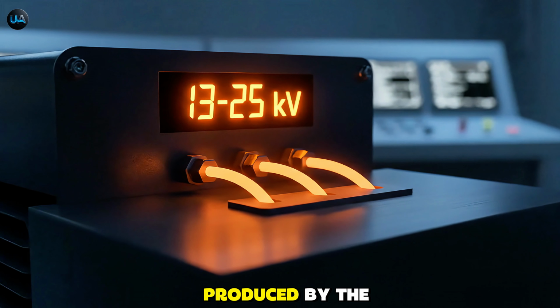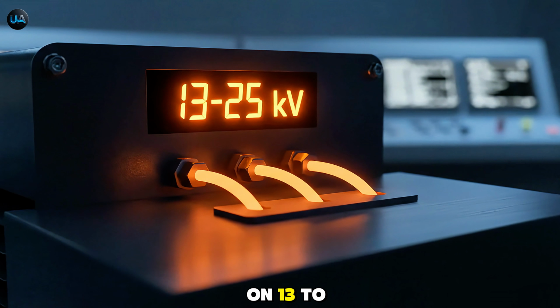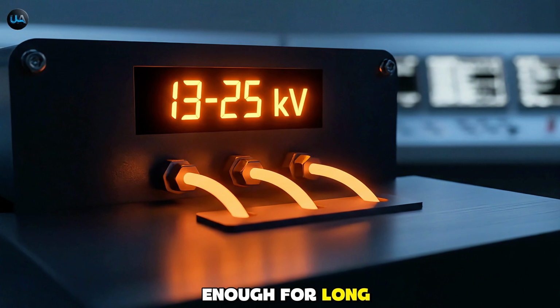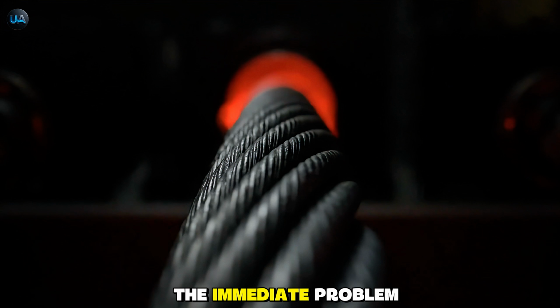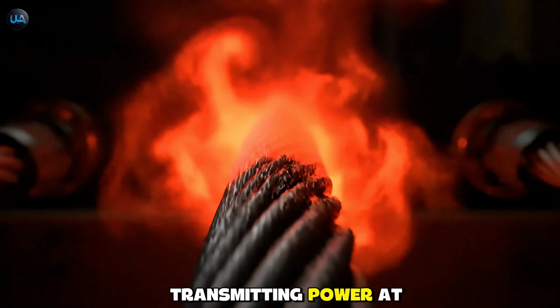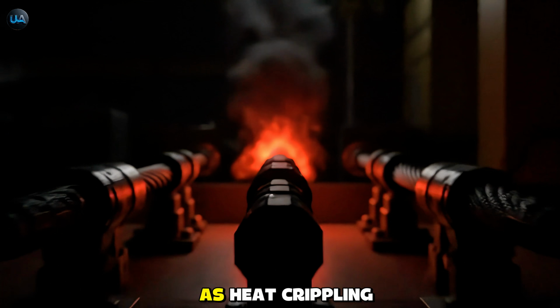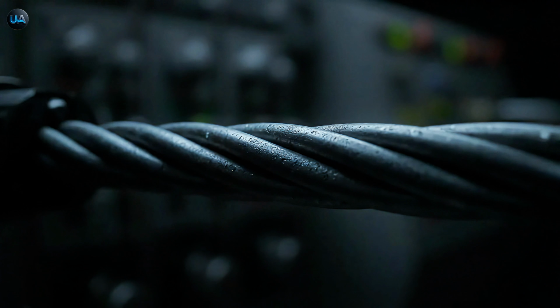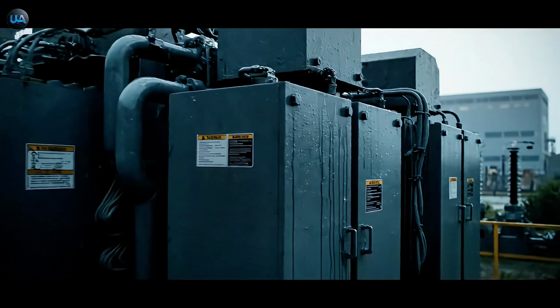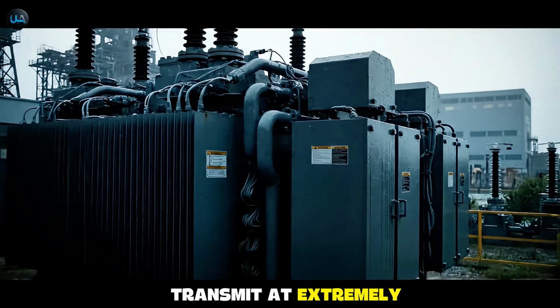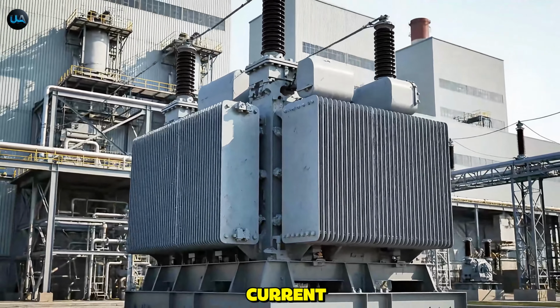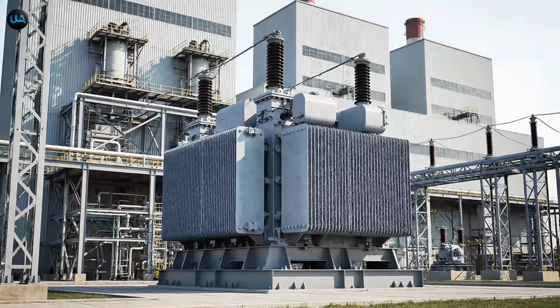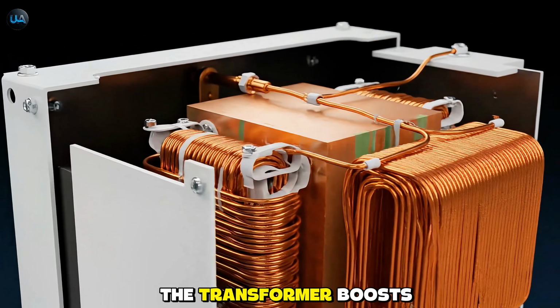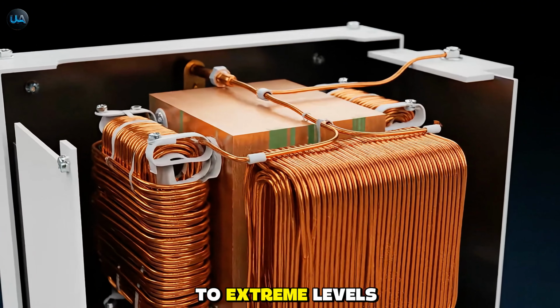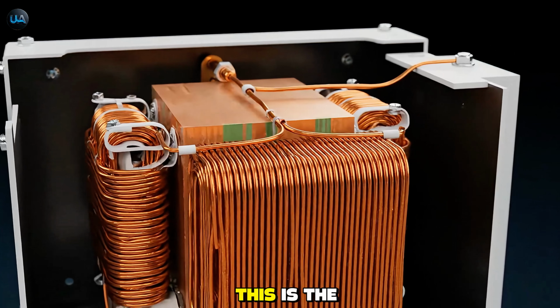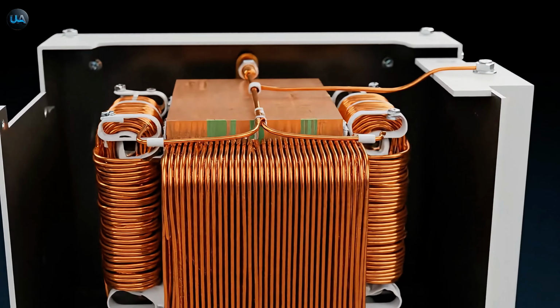The initial voltage produced by the generator is typically moderate, 13 to 25 kilovolts. This is not enough for long-distance travel. The immediate problem is line loss. Transmitting power at low voltage results in massive energy waste as heat, crippling the system's efficiency. The engineering solution: transmit at extremely high voltage, drastically lowering the current. This relies on the step-up transformer. The transformer boosts the voltage from 25 kilovolts to extreme levels, up to 500 kilovolts. This is the first, most crucial transformation.